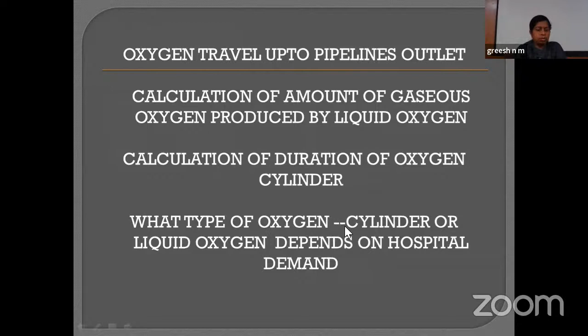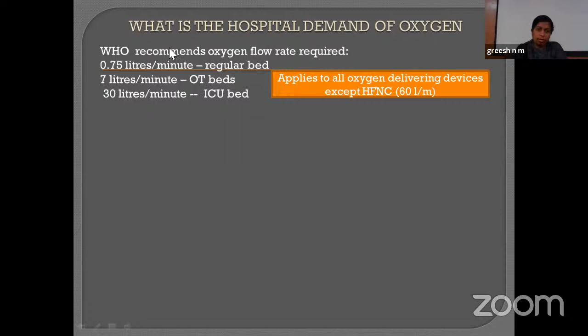WHO recommends a certain flow rate for different types of beds in the hospital. That is around 0.75 liters per minute for a regular bed, 7 liters per minute for OT beds, and 30 liters per minute for ICU beds. This applies to all varieties of oxygen delivering devices except HFNC, for which there is a very high flow rate of around 60 liters per minute. And I just want to say that whatever WHO recommends is not universal. It varies from region to region, depending upon the pandemic condition of a respiratory disease and the government rules in a particular area.